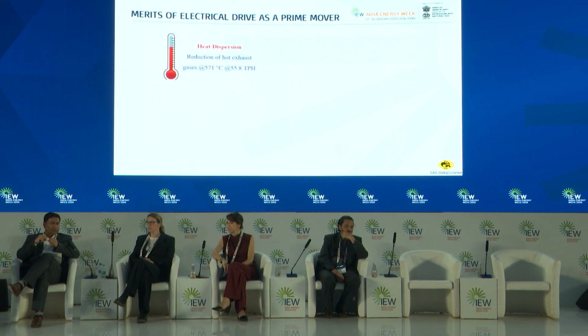Now let's talk about the merits of the electric drive compared to the gas turbine. The first is heat dispersion: reduction of hot gases at 55.8 TPH, at a temperature of 571 degrees. The second and most impactful is the reduction of CO2 emissions, to the tune of 12,000 tons per annum. The capex cost for the project was around 17 crores. We have lowered the one-time cost by about 90% compared to the turbine.